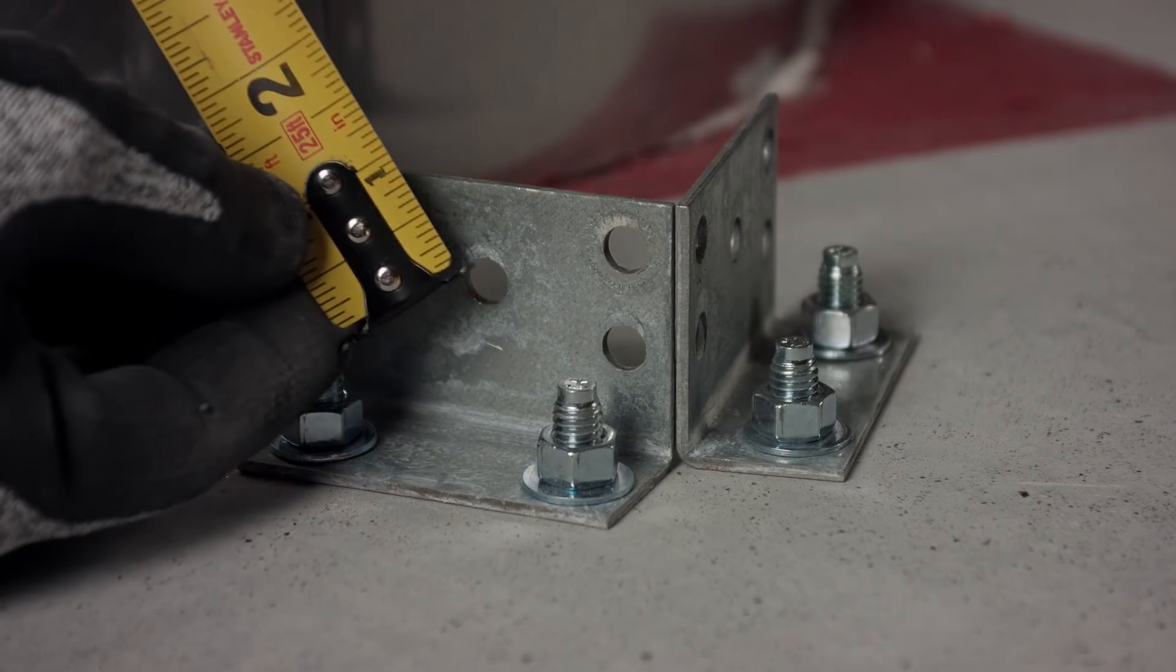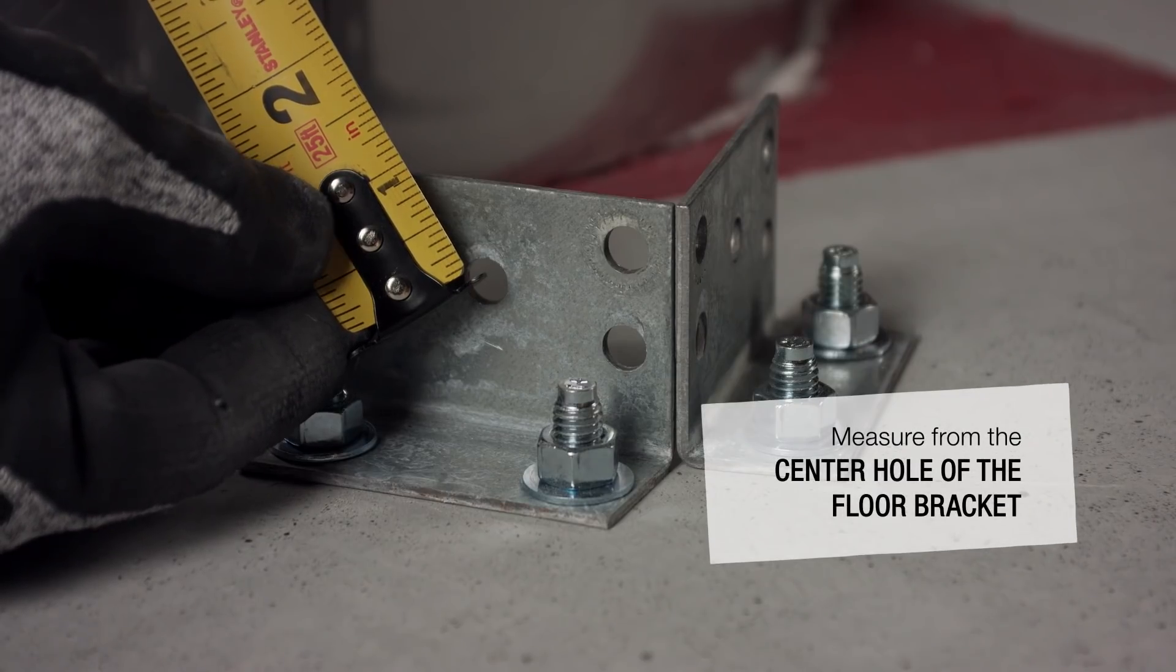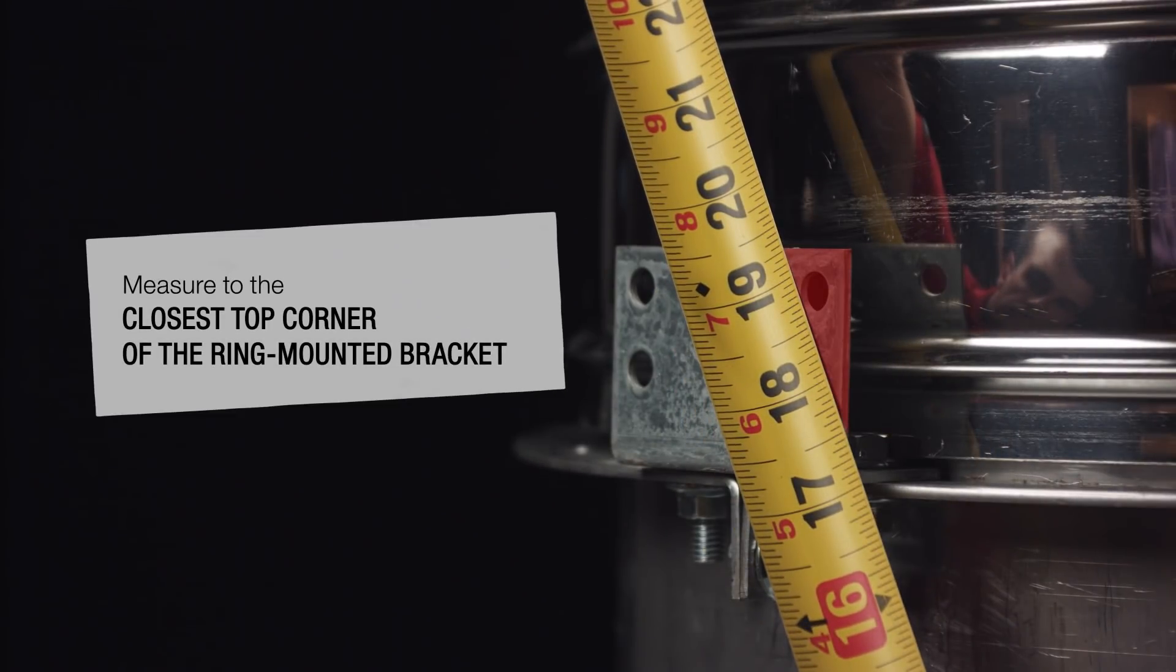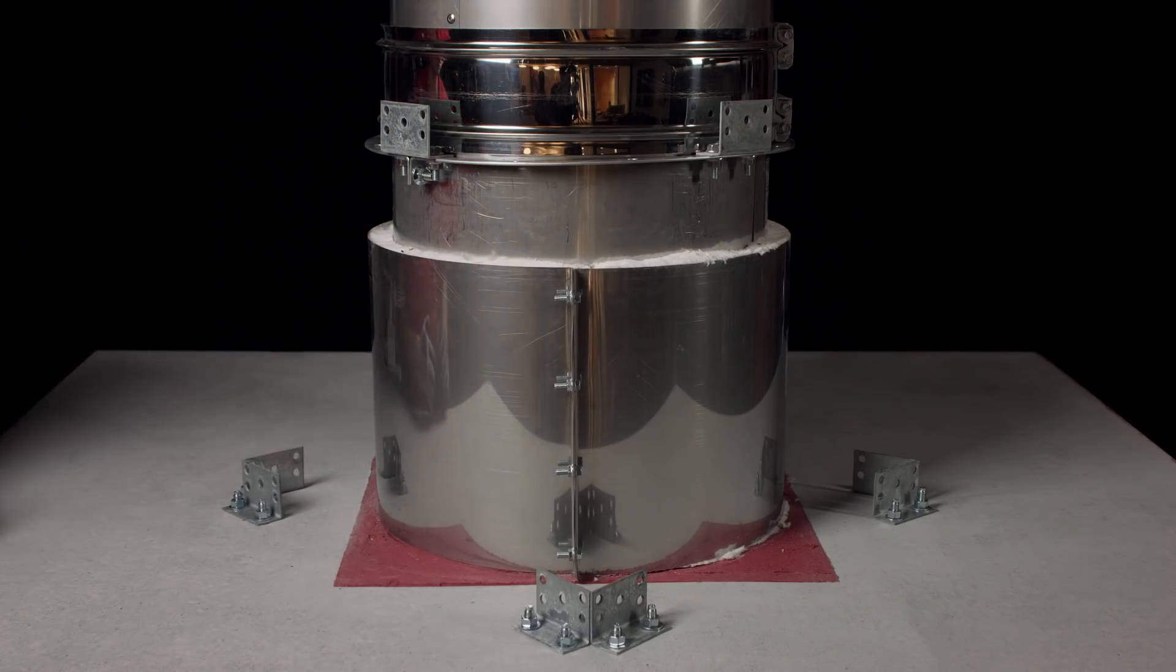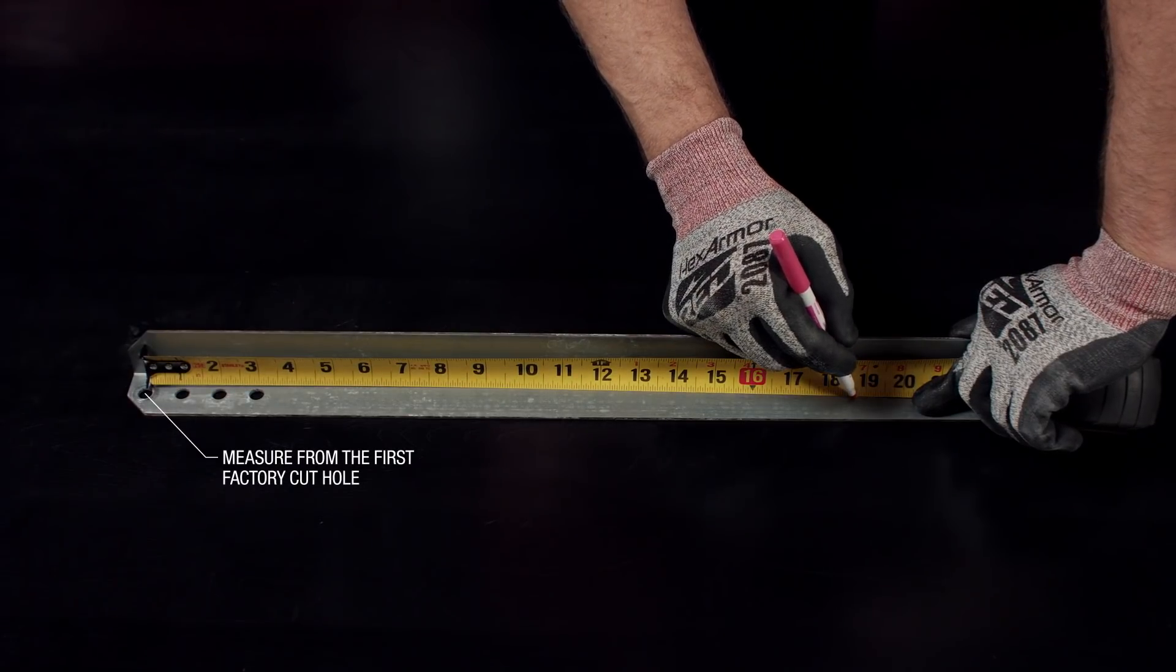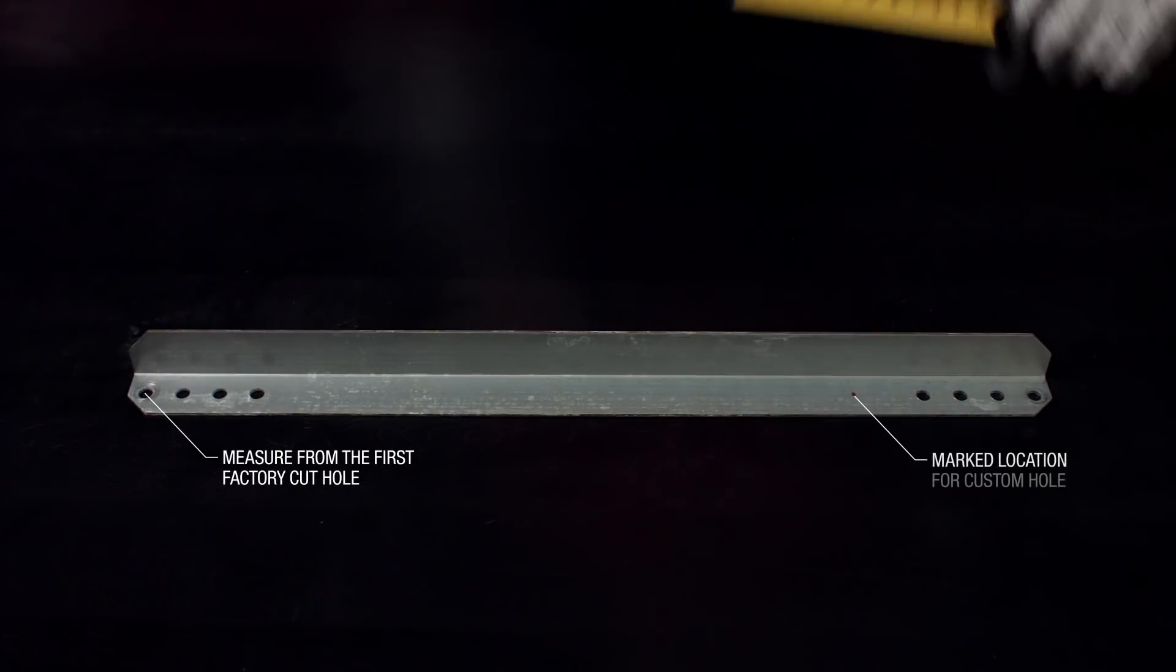More specifically, you should measure from the center hole of the floor bracket to the closest top corner of the ring-mounted bracket. You will then use this measurement to mark the spot for one custom hole in each of the support legs, starting from the first factory cut hole.